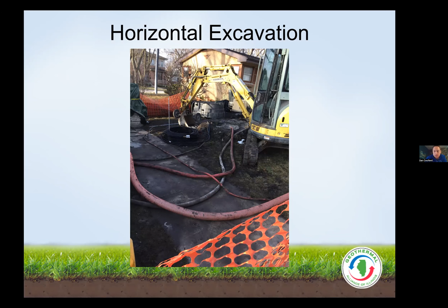Then they take the same size pipe as the boreholes, in this case 3/4 inch - you can see 8 pipes in the left picture, 2 for each borehole. They connect them by fusing, which is basically melting the plastic together with specific equipment, to each header pipe. Now we have a supply and return system that pushes the water out, equally distributes it through the 4 boreholes, and it runs all the way down and back up, dissipating or consuming a little heat in the process.